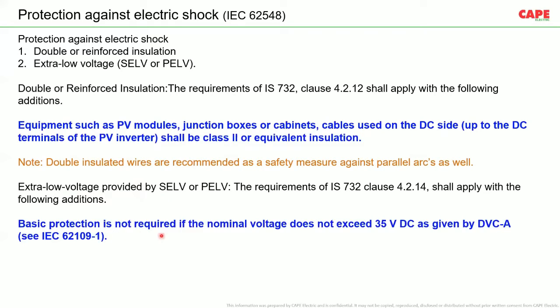Also, basic protection is not required if the nominal voltage is lesser than 35 volt. But of course, most of the time, the DC side operating voltage is much higher than 120 volt. So the effective shock protective measure is double or reinforced insulation, double insulation.